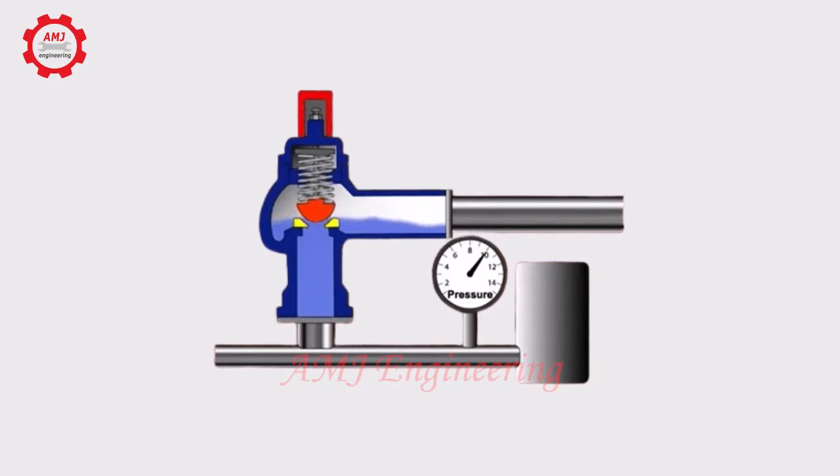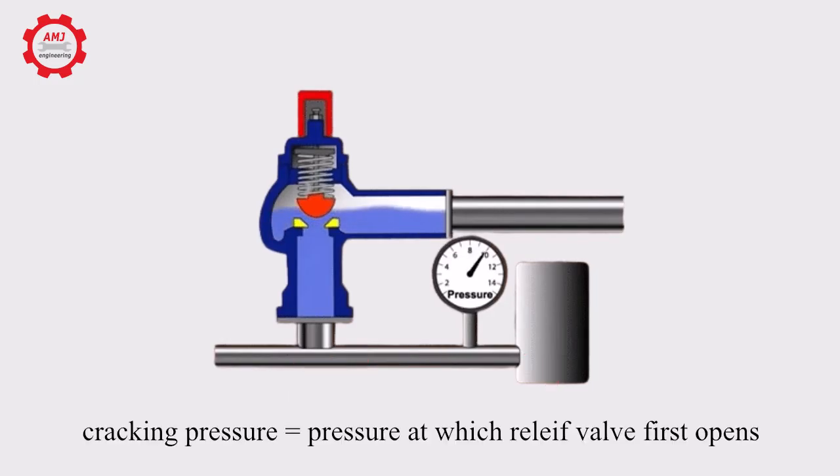The spring reseats the ball or poppet when enough fluid is released to drop system pressure below the setting of the valve spring. The pressure at which a relief valve first opens to allow fluid to flow through is known as cracking pressure.